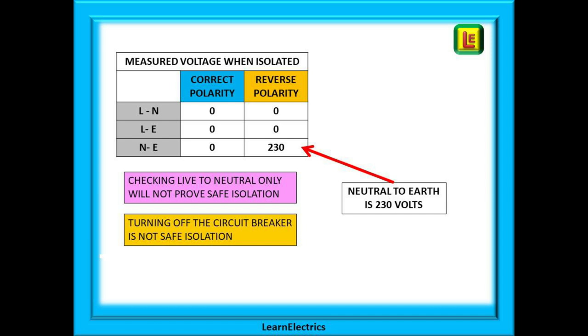If we only measured live to neutral it would not tell us the full story. It would not guarantee safety if the circuit was reverse wired. Look at this table. If we isolated the light circuit at the MCB and checked only the live to neutral voltage, we would find that the voltage was zero volts whether the circuit was correctly wired or reverse wired. Test further. The live to earth is zero also and that seems correct. But the voltage between neutral and earth is 230 volts. This is the danger. Relying on just a live to neutral check when isolating is not enough.